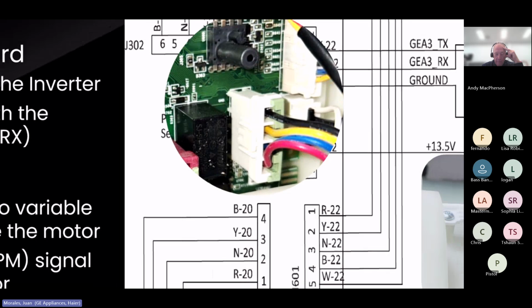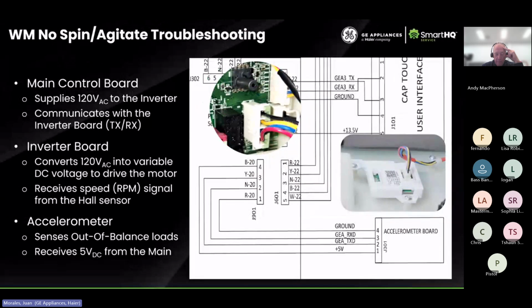So that, my friends, would be pretty much everything in terms of troubleshooting, or as far as what you have control over, when it comes to a no spin condition. But there's one thing we didn't talk about in this circuitry: how do you troubleshoot the feedback signal, the RPMs? How do you troubleshoot that hall sensor, the signal that travels from the motor to the inverter all the way to the main? The truth is there's no way unless you carry an oscilloscope.